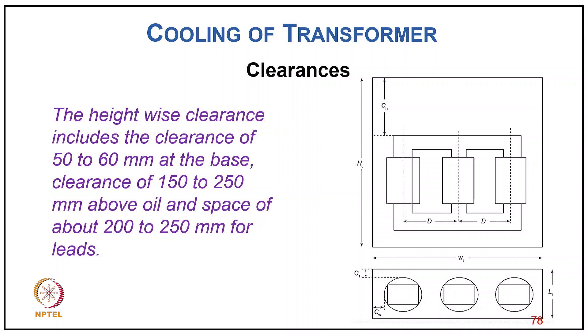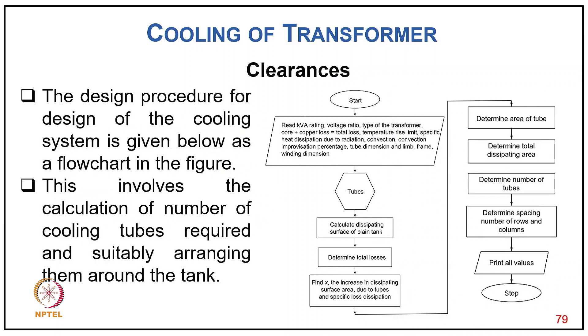The design procedure for the cooling system is given as a flowchart. Steps include: input transformer design data and specifications; calculate tank surface area; determine losses; find X for required increased surface area; determine tube area; determine total surface area; determine number of tubes; determine spacing, rows and columns; then output and stop.